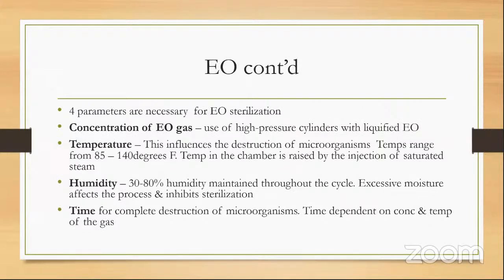So there are four parameters necessary for ethylene oxide sterilization. One has to do with the concentration of the gas itself. So they use high pressure cylinders that have liquefied ethylene oxide in it. The temperature is important, and there is actually some steam involved in it. But compared to steam sterilization, these temperatures are low, 85 to 140 degrees Fahrenheit.